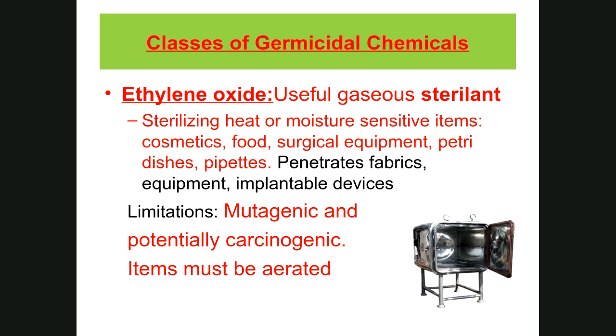Ethylene oxide, this is a gas, and it is used as a sterilant. You do need to use it in a special chamber, similar to an autoclave, except that it's using ethylene oxide instead of steam. It is used to sterilize heat-sensitive items, intricate items that are more difficult to sterilize with an autoclave. Problem, it is a mutagen, potential carcinogen. So whatever is sterilized using ethylene oxide will have to be aerated afterwards to get rid of the gas.